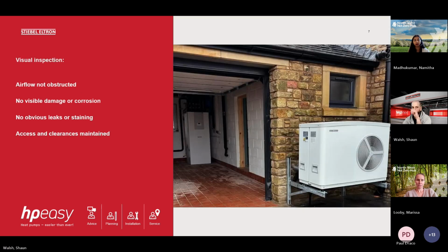So when we're looking at visual inspection, quick example here. If we were doing a visual inspection of this typical install here, the first thing we'd be looking for is, do we have minimum clearances for the machine? Is it accessible and does it allow you to do the work? So in this example, we can see there's clearly enough room at the back for us to do a visual check of the evaporator fan. There's plenty of space underneath, so we can check if the condensate's clear.